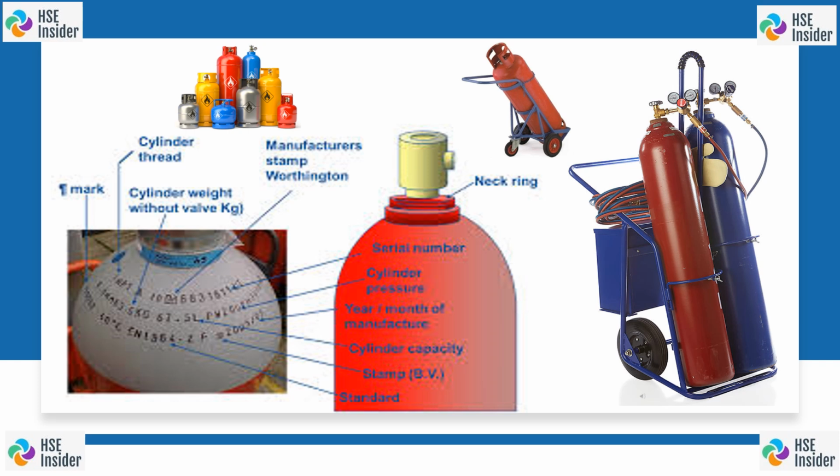Then come to the next important requirement, safety relief devices. For cylinders manufactured in India, the safety relief devices should be fitted in their bodies, and the safety relief devices should be maintained in accordance with the Indian Standard requirement of IS 5903.